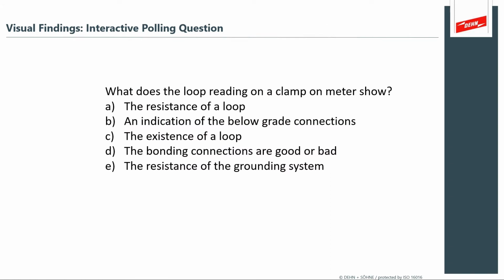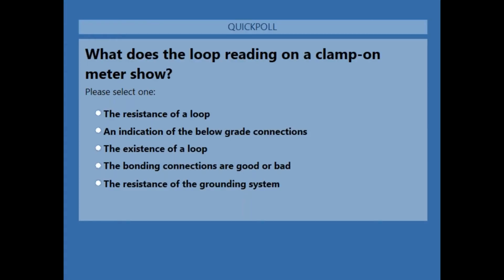So we're moving on to an extremely popular technical aspect. What does the loop reading on a clamp-on meter show? And you know my affinity for trick questions. It provides a resistance of a loop. It indicates below ground connections that you can't otherwise see visually. It shows the existence of a loop. It allows you to evaluate if bonding connections are good or bad. And it shows the resistance of the ground system. Now, this is a really important trick question. So I'd like to see what the audience thinks that the meter gives them. What does that tool do for you?